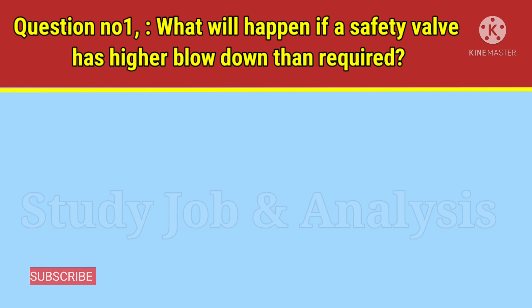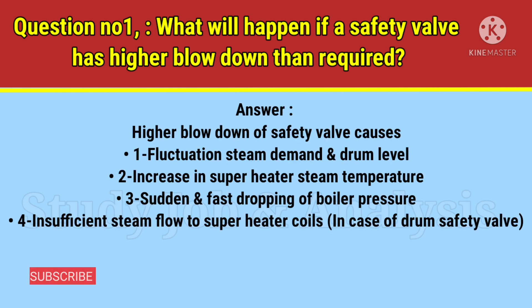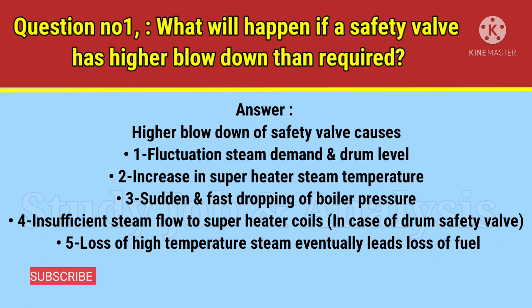Answer: Higher blowdown of a safety valve causes: one, fluctuation in steam demand and drum level; two, increase in superheater steam temperature; three, sudden and fast dropping of boiler pressure; four, insufficient steam flow to superheater coils in case of drum safety valve; five, loss of high temperature steam, which eventually leads to loss of fuel.